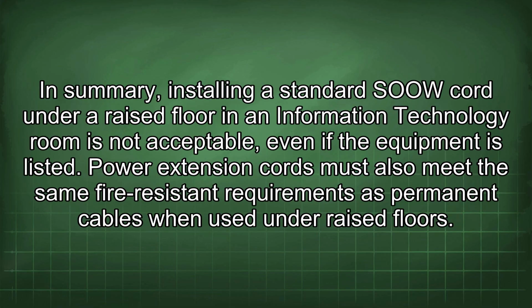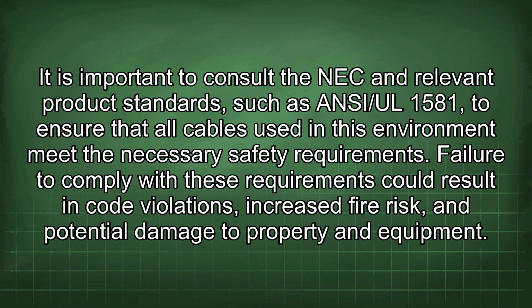In summary, installing a standard SOOW cord under a raised floor in an information technology room is not acceptable, even if the equipment is listed. Power extension cords must also meet the same fire-resistant requirements as permanent cables when used under raised floors. It is important to consult the NEC and relevant product standards such as ANSI/UL 1581 to ensure that all cables used in this environment meet the necessary safety requirements.